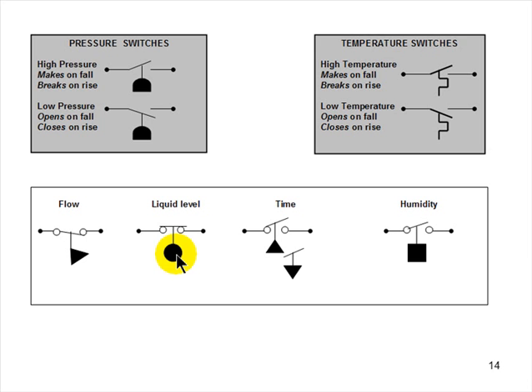This is a float switch you use in a condensate pump. This is the second switch. The first switch, as the level rises, it makes and causes the motor to come on and pump out the reservoir in the condensate pump. If the motor fails for some reason, the switch doesn't know that, but the level keeps rising, and what will happen then, it will open up, and it will make another set of contacts and cause a light to come on, or maybe you got the compressor Y leg broken across there. It'll shut the cooling off.